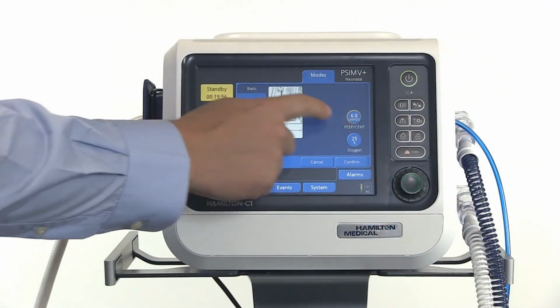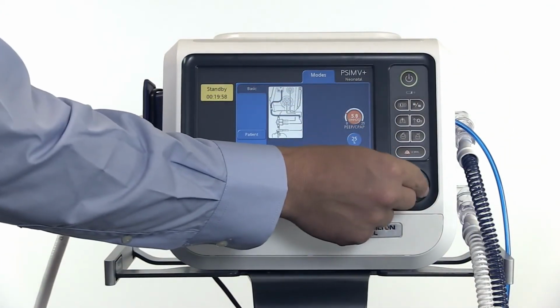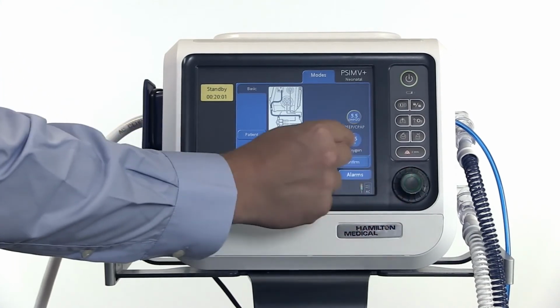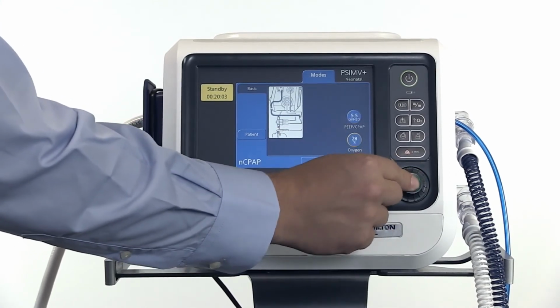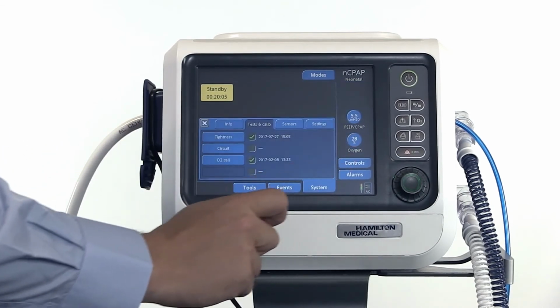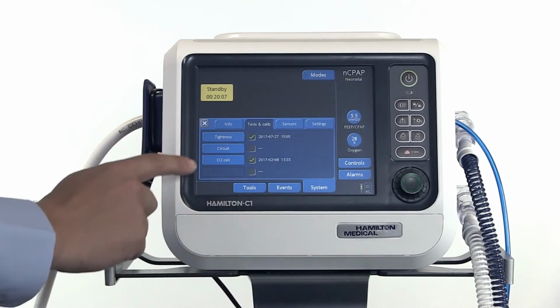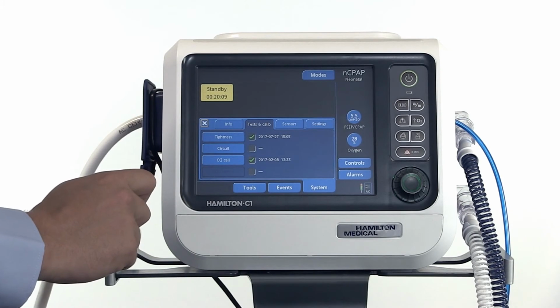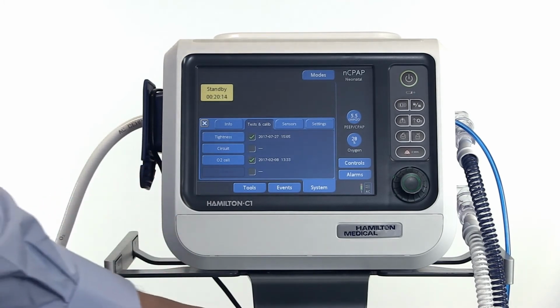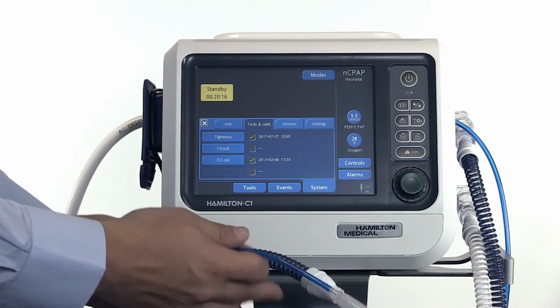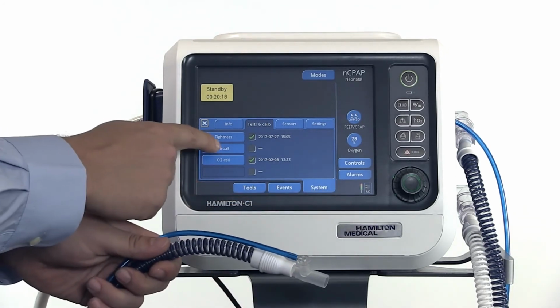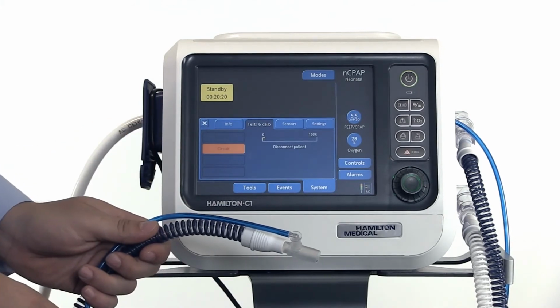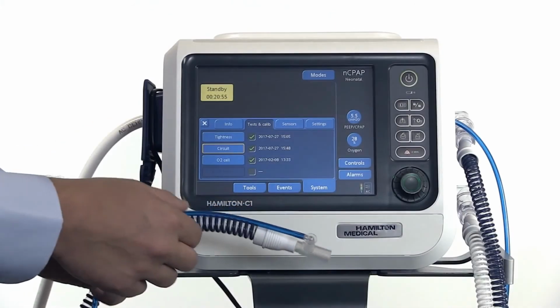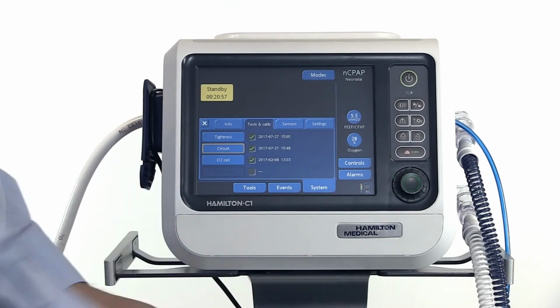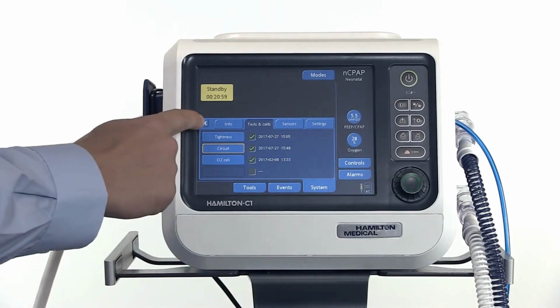Now check the default settings for PEEP, CPAP and oxygen, and adjust them if necessary. Save your adjustments with confirm. The pre-op check window opens automatically. For optimal tube resistance compensation, you need to calibrate the circuit. Simply follow the instructions on the screen. After calibration has been completed successfully, close the window and check your alarm settings.